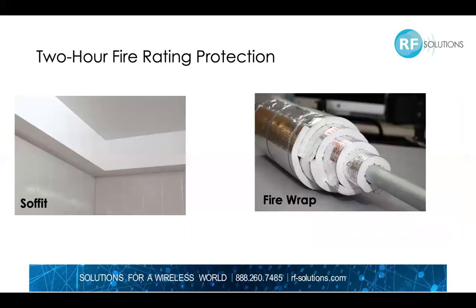The NFPA and IFC codes we discussed earlier require cabling to be protected for at least 2 hours of exposure to high temperatures. These are two examples of providing 2-hour fire rating of cable runs: constructing soffits and using fire wrap.